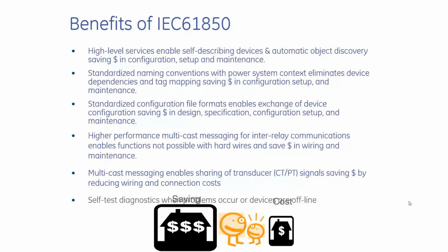It's more of an object-oriented language, or a language that describes a lot of various aspects that we use, and the advantage is high speed, a lot of data that we can transfer with it. We can do monitoring, diagnostics, protection tripping, getting CT, VT information directly from the substation yard without wiring CT and VT cables out there. So it gives us a lot of advantages, and it is future-proof. It takes advantage of current technology, specifically Ethernet technology, and we expect Ethernet technology to evolve and 61850 to evolve with it as we go forward.